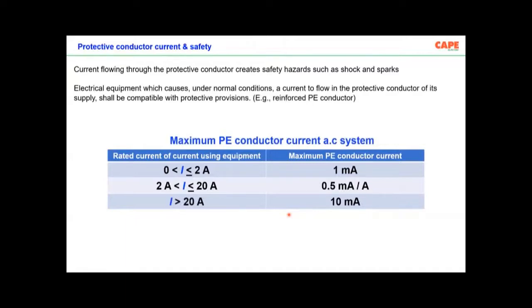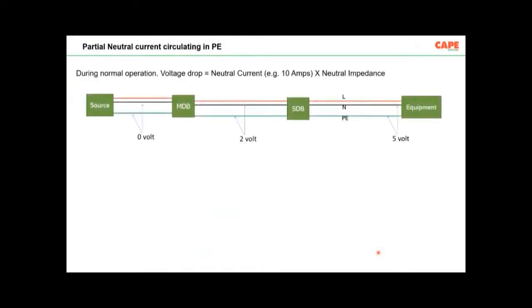If the current flow is exceeding these limits, then we are supposed to have additional earthing provisions such as a reinforced PE conductor. In order to ensure that the current is lesser than this particular limit, every electrical installation is supposed to make a test of insulation resistance. How to make the insulation resistance test? You must disconnect your equipment. You must test the insulation resistance of your wiring, including your panel board. You must disconnect your earthing, and you must test the insulation resistance between neutral and protective earthing conductors. The minimum resistance required is 1 megohm. If the resistance is lesser than 1 megohm, then your electrical installation is not in a good condition.